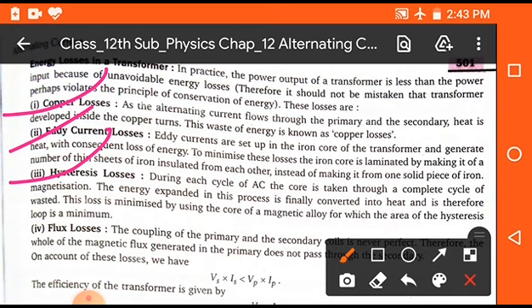Now, hysteresis loss, which is important and generally asked in board exams. During each cycle of AC, the core is taken through a complete cycle of magnetization. The energy expended in this process is finally converted into heat and is therefore wastage. This loss is minimized by using a core of magnetic alloy for which the area of the hysteresis loop is minimum, meaning we can reduce this loss by making the hysteresis curve very minimum.